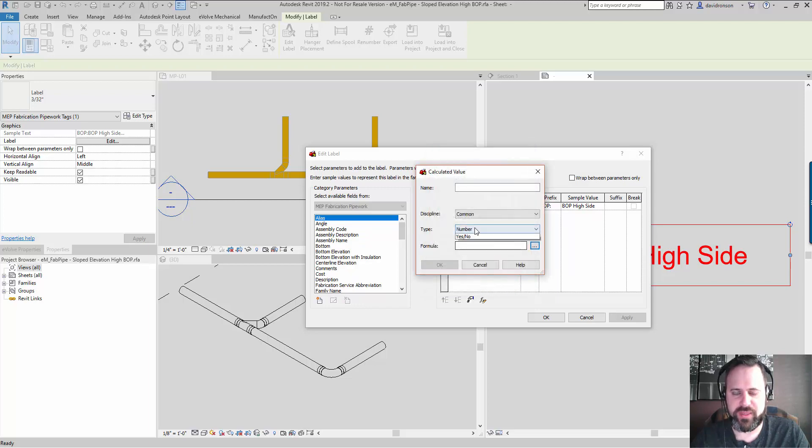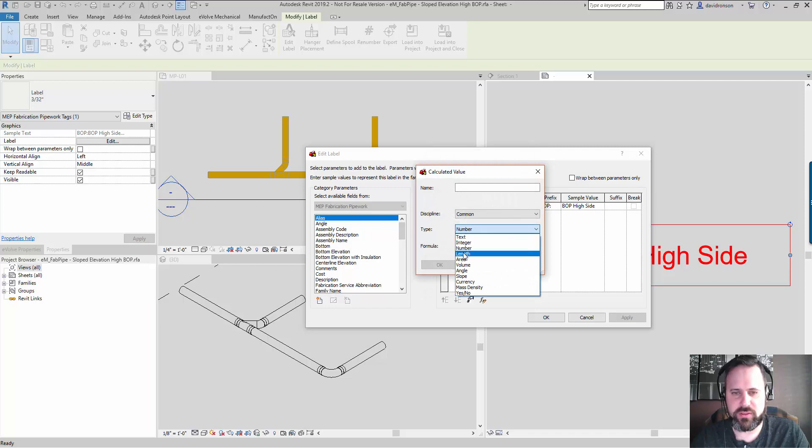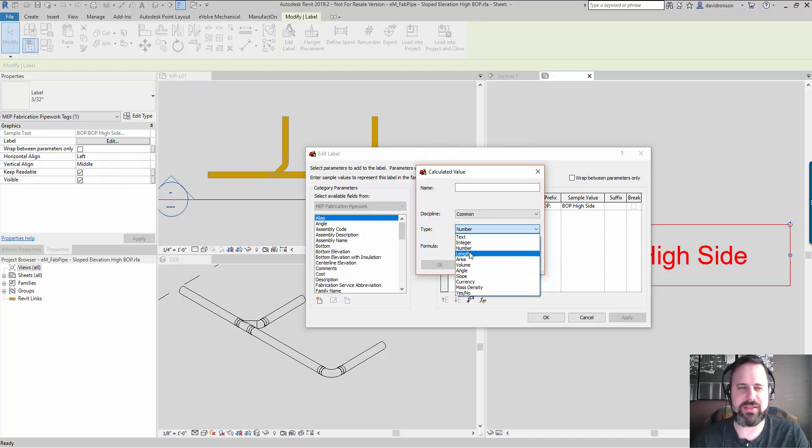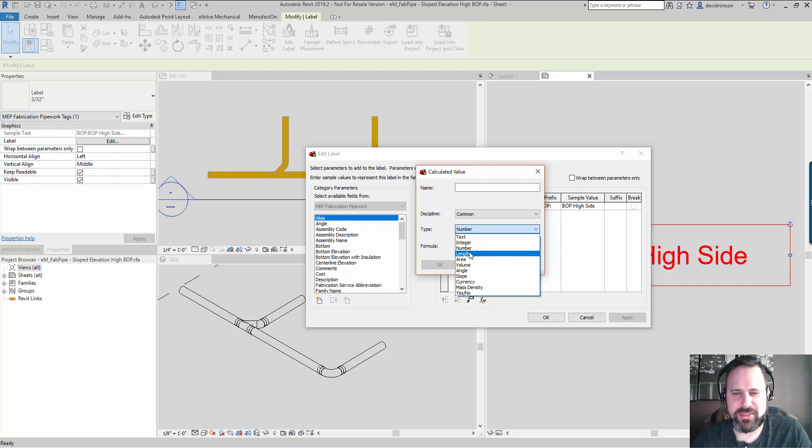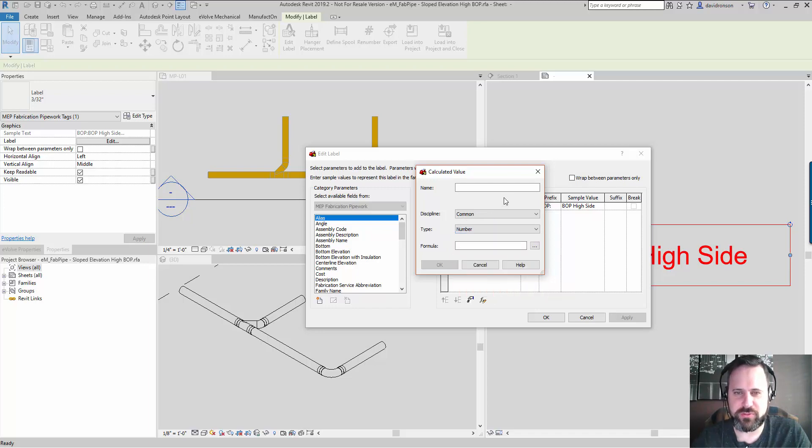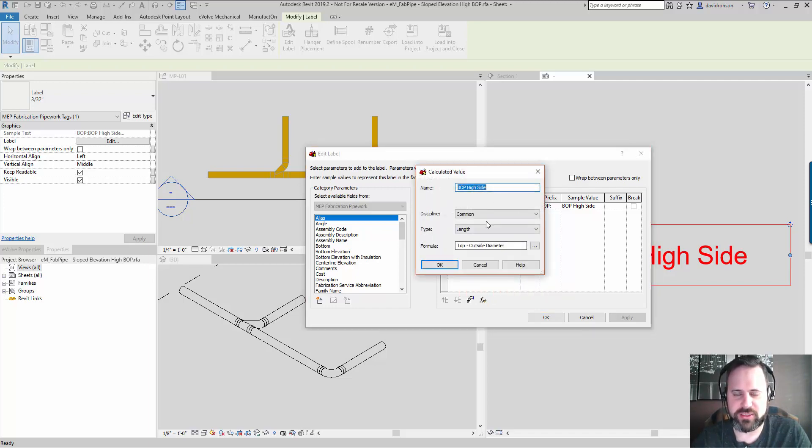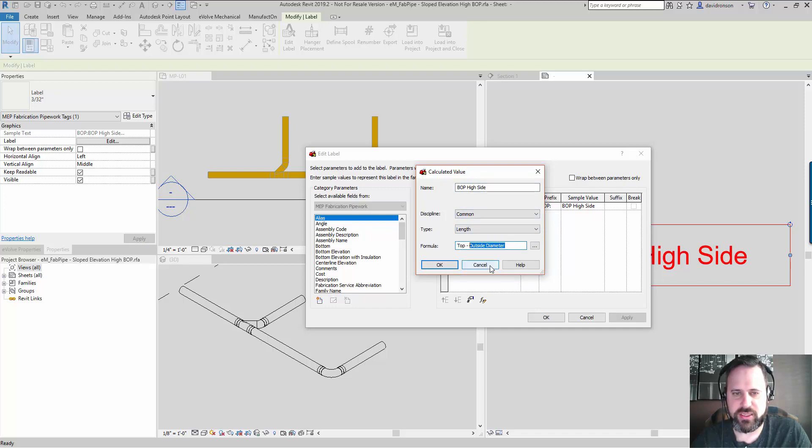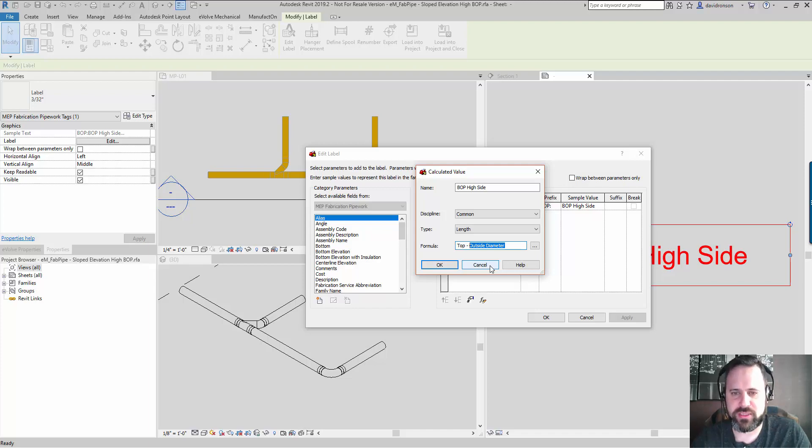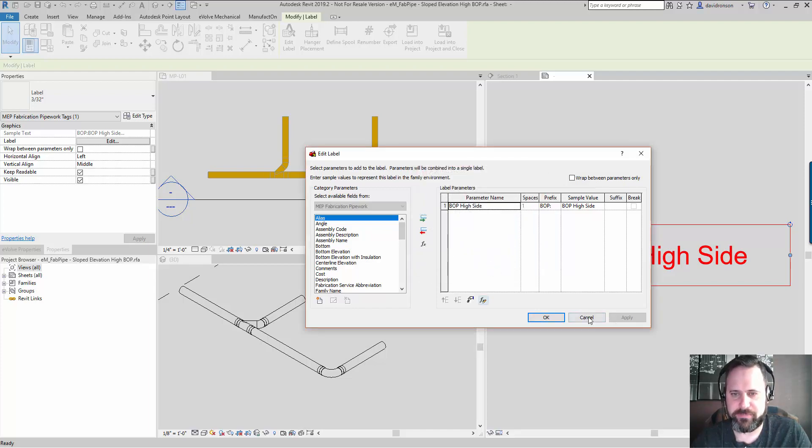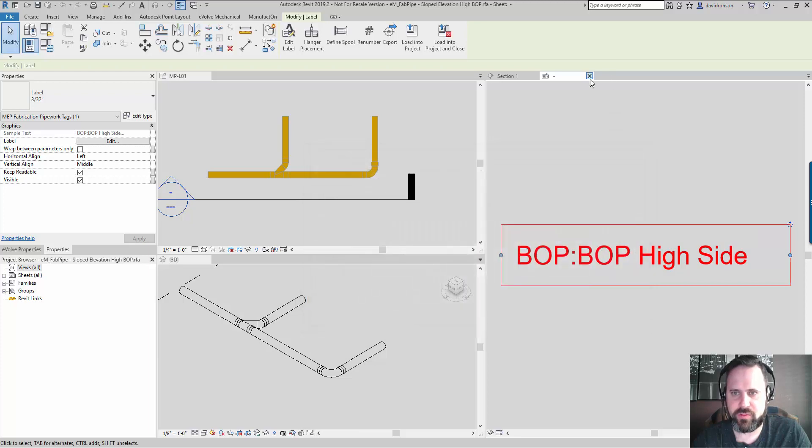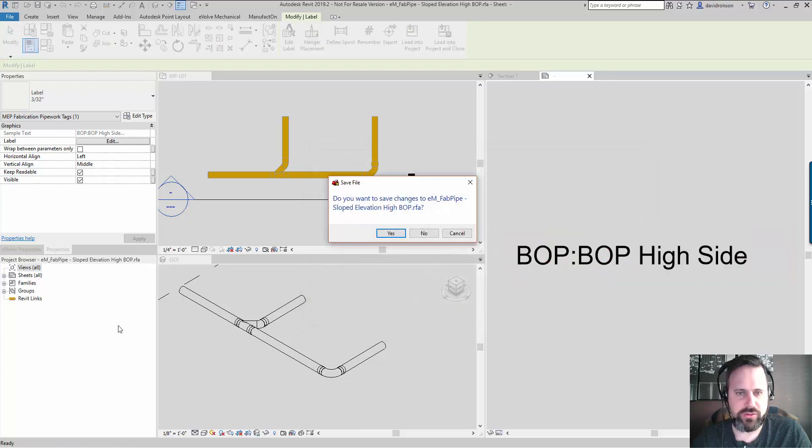The biggest thing is to make sure you have the right type. When I first did this I did it against number, it kept saying invalid units or something like that, so I had to use length. So I'm doing a calculation of two length fields, which makes sense. This is the name of the parameter, and then formula: top side minus the outside diameter - that gives me the bottom side BOP on the high side of the pipe.